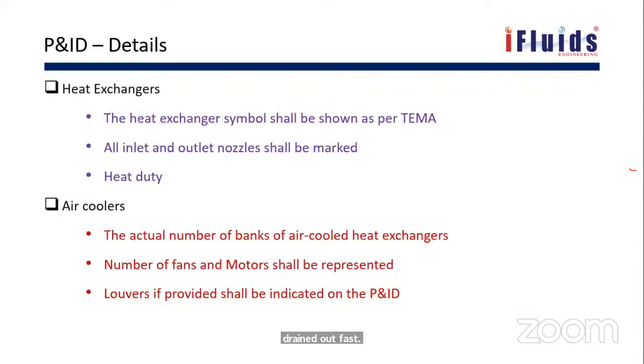And the heat exchanger symbol shall be shown as per TEMA. Actually, TEMA is one kind of standard; there are many industrial exchanger manufacturers with different standards. So whatever standard is followed, that particular symbol we need to mention. And then all the inlet and outlet nozzles shall be marked, and the heat duty will be mentioned for the exchanger.